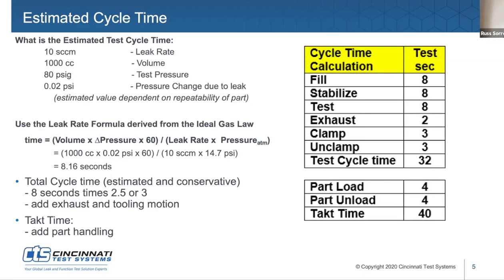I think some of the pushback that we get, as I think back on the many times that we've gone through this calculation, is that we want to be conservative, and the tendency is that a customer will want to match whatever the cycle time is for their overall takt time. They want to try to match the leak test into that takt time, and that's kind of the tail wagging the dog as it relates to achieving, so we do this because we want to achieve a specific gauge R&R, right? The ideal gauge R&R. Yeah, absolutely. You don't want to overstate a quick cycle time and then come back and have to add multiple stations, because that's an economic factor that may not be budgeted for later in a project. And everyone's got to know the end goal and the end understanding when you start this. So tell me the reality, not the ideal, right?